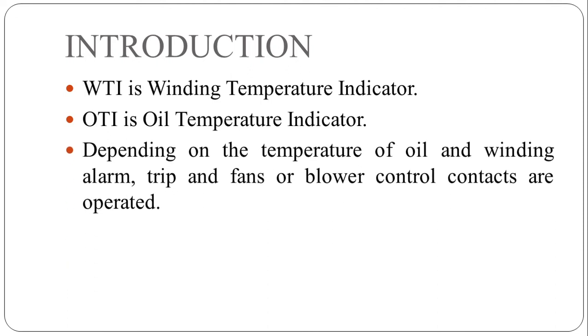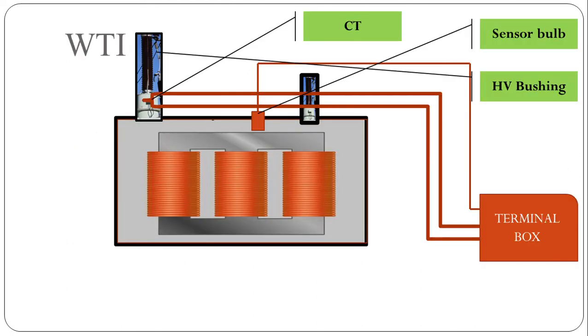Depending on the temperature of oil and winding, alarm trip and fan control contacts are operated. See this is the diagram of transformer. Here we can see that core and windings are enclosed inside the transformer tank. This is bushing of transformer and a current transformer is placed at the bottom of this bushing. The terminals from this current transformer are brought out to the terminal box and this is a sensor bulb. Now we will see the function of this current transformer and this sensor bulb.